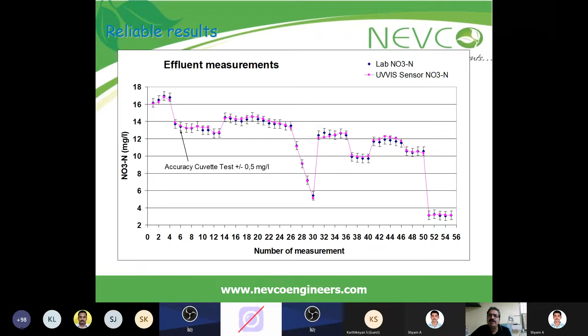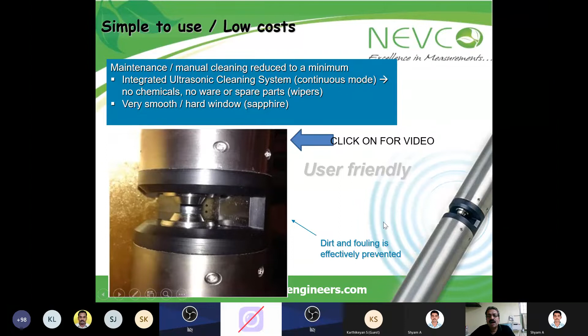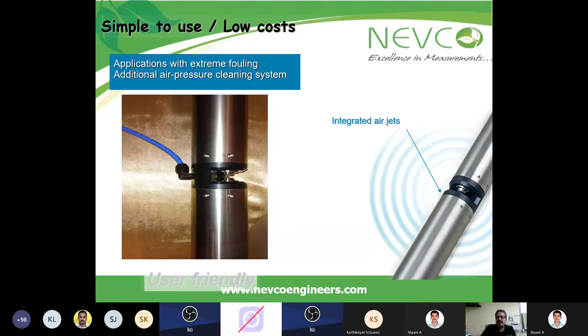Then this has maintenance-free ultrasonic cleaning. Manual cleaning is reduced to a minimum, but here integrated ultrasonic cleaning is available. You can say continuous mode. So no chemicals, no wear or spare parts, wipers not required. Very smooth, hard sapphire glass window this is. And here there is a small video. For extreme fouling conditions, you can give additional air pressure cleaning also, air jet cleaning is also possible. So you can add an integrated air jet, but the ultrasonic cleaning system will take care of any issue. You see, this is a permanent ultrasonic cleaning.